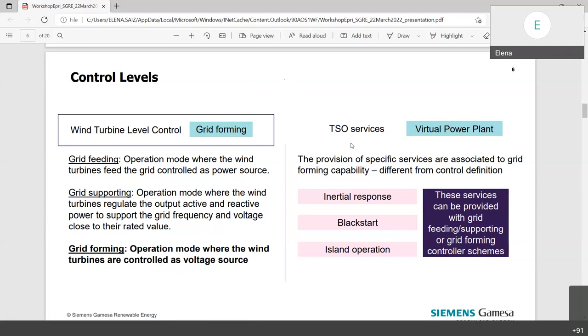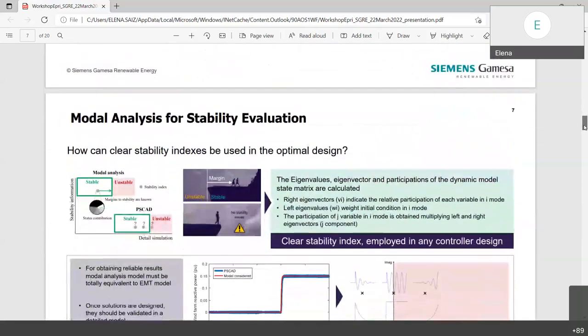As we have commented, we should distinguish the different controls regarding the converter operation from the services that we need our wind turbine to provide. Here we can talk about inertia response, black start, island operation. We should be aware that a service such as inertia response can also be provided with grid feeding or grid supporting. The only problem is the speed of that inertia response. If we really want a very, very fast inertia response, for sure we are going to need a grid forming control, but the regulator should define the performance of the wind turbine and the manufacturer proposes the controller to be implemented to guarantee that the service is provided.